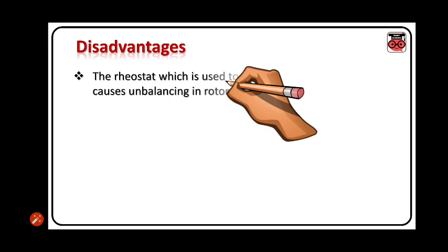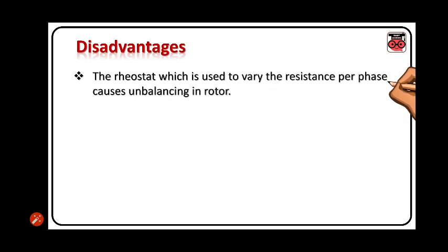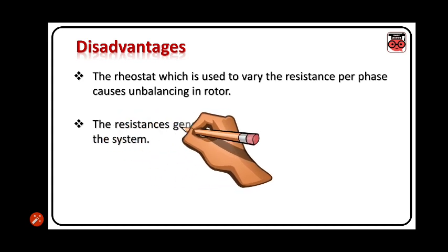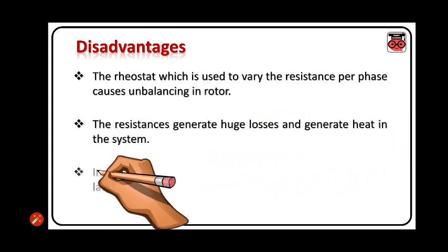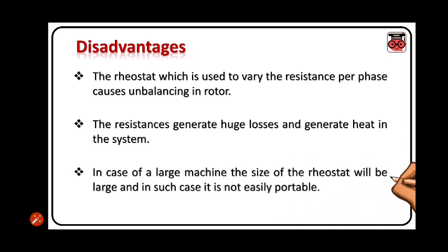Disadvantages: The rheostat which is used to vary the resistance per phase causes unbalancing in rotor. The resistance generates huge loss and generates heat in the system. In case of large machines, the size of rheostat will be large and in such case it is not easily portable.